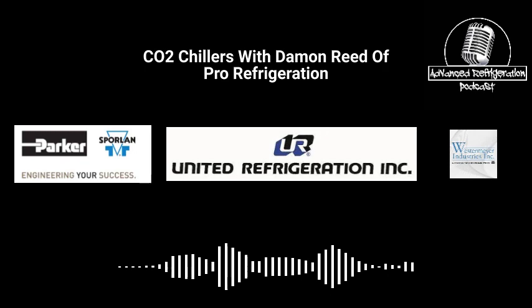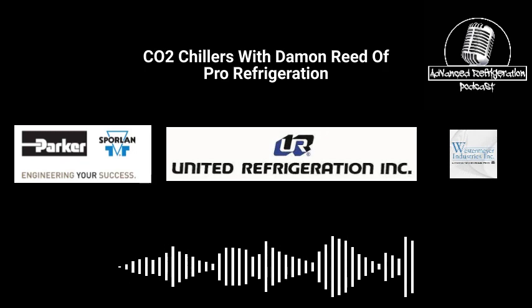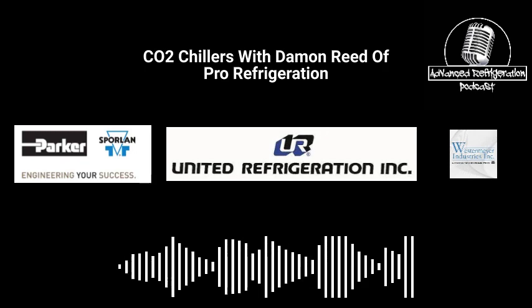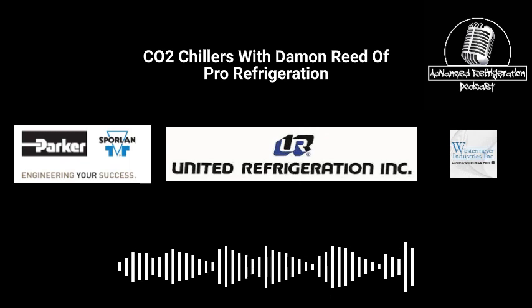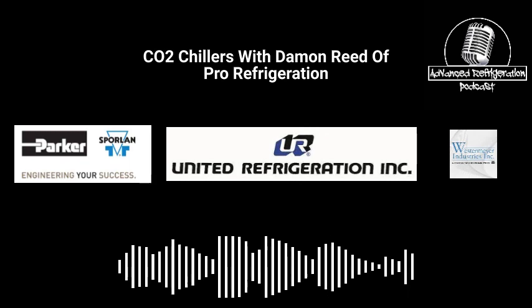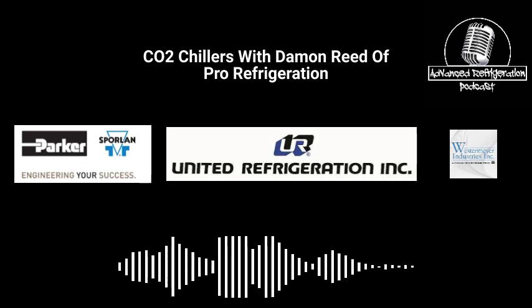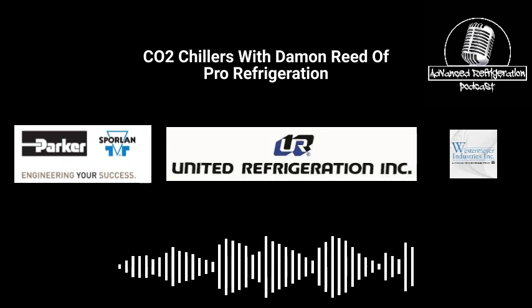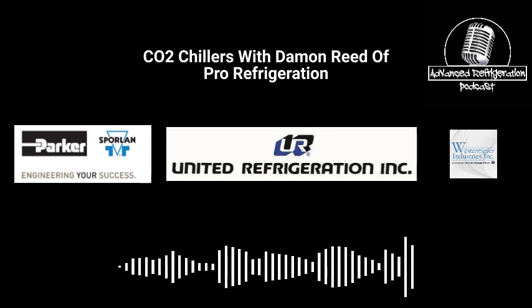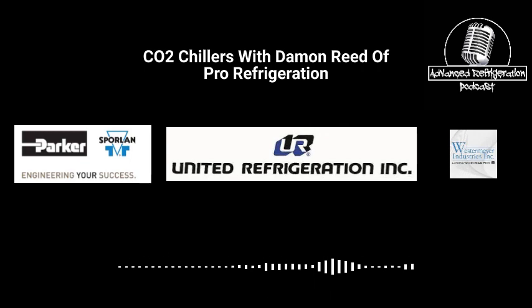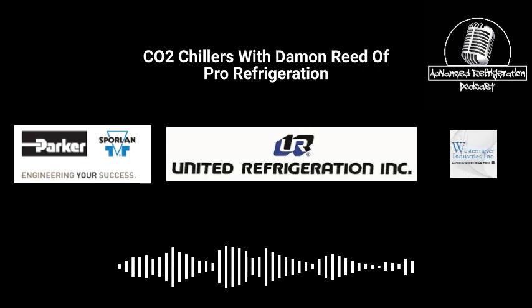So let's talk about the oil system for a little bit, because I have a couple questions. We have a ton of problems when these racks shut down with the oil management. So how are you guys doing your oil system? Are you using OMBs or OMCs, or the Danfoss controller to fill oil pots? It's both. We're using the OMCs on the compressors. Those are our regulators for the crankcases.